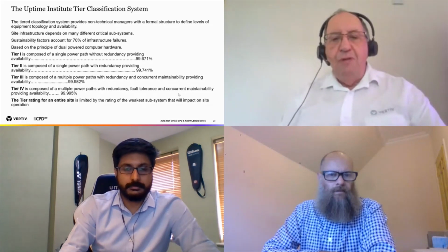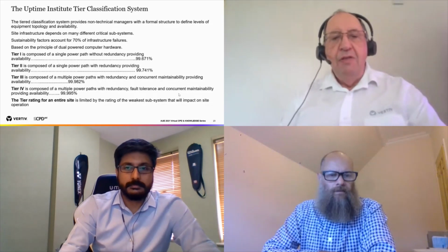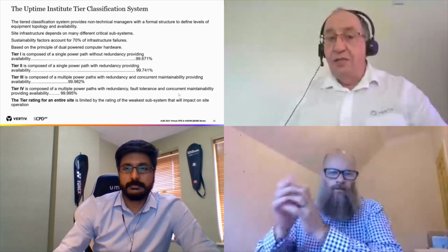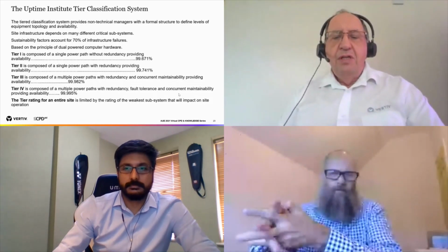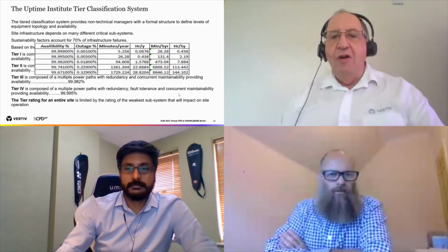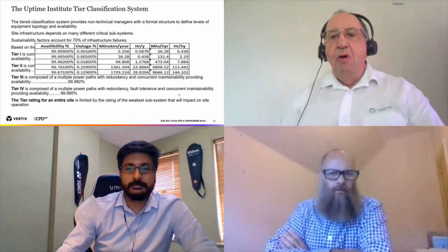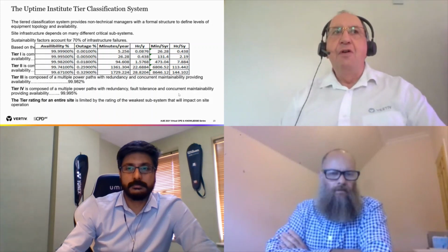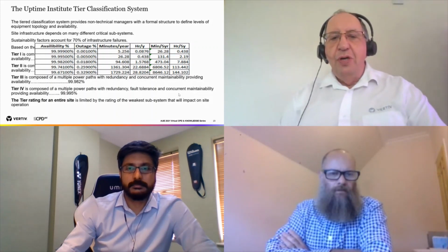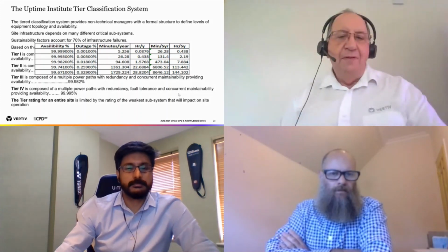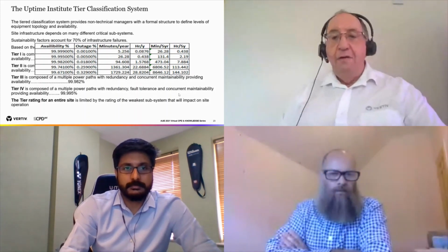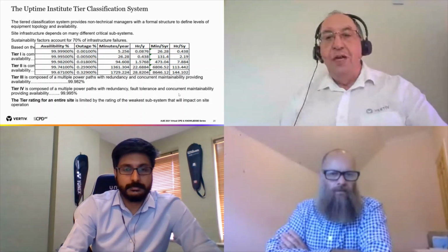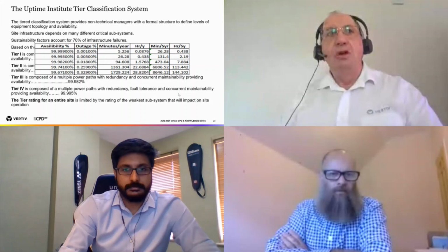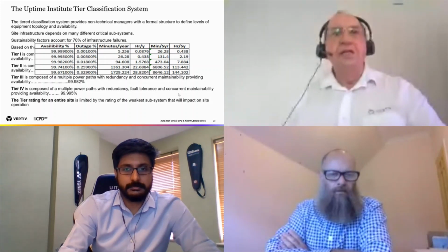So just remember that these ratings are limited by the rating of the weakest subsystem that will impact on the load. So this could be mechanical, electrical, it could even be the security system. So what does it mean? It means that if you're 99.999, you have 5 minutes a year, or 0.43 hours every 5 years of the service being off. If we're talking about tier 1, maybe we're talking about 1,729 minutes per year off, or 144 hours over 5 years. So it depends on what your client is looking for as to which system you need to design to.